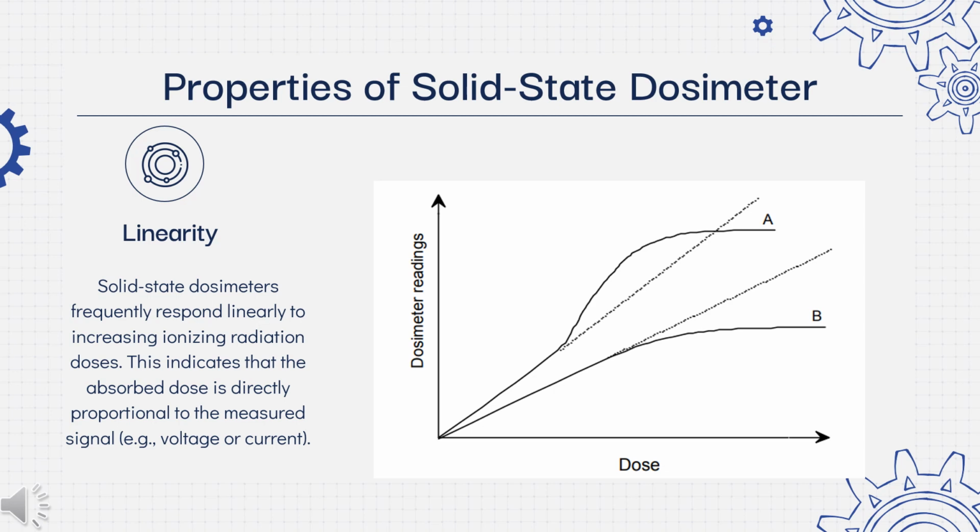Two typical examples of response characteristics of a dosimetry system are sketched in this figure. Curve A first exhibits linearity with dose, then a supralinear behavior, and finally saturation. But curve B first exhibits linearity and then saturation at high doses. In general, nonlinear behavior should be corrected for.